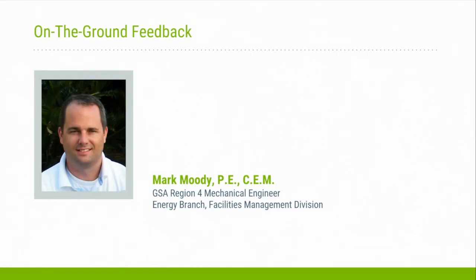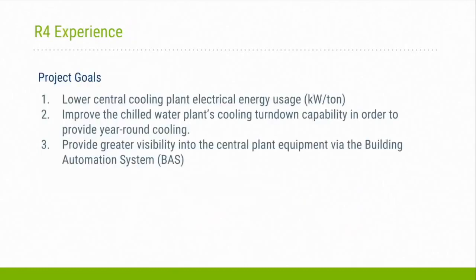We had 3 goals for installing demand flow at the FMJ complex. First, lower central cooling plant electrical energy usage, thereby reducing the building's energy use intensity, or EUI. Second, improve the chill water plant's cooling turndown capability in order to provide year-round cooling. This should help improve tenant comfort and help resolve some tenant complaints we were having. And third, provide greater visibility into the central plant equipment via the building automation system. This should help improve system monitoring and troubleshooting.